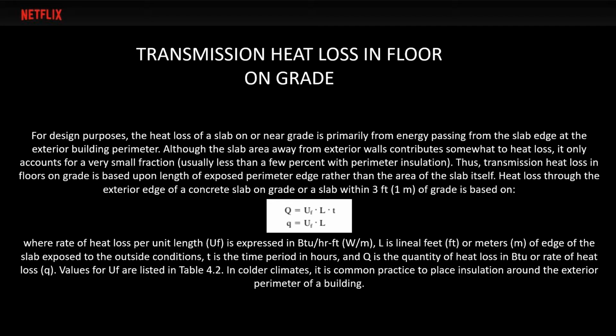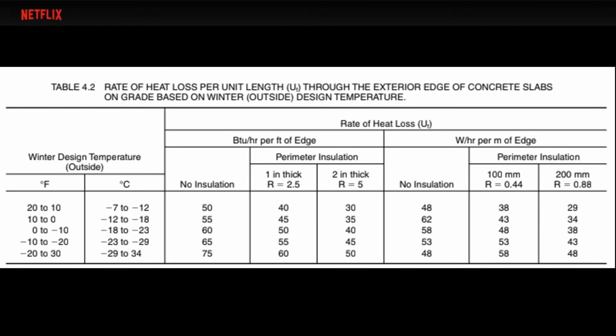So, here is the formula again, where the rate of heat loss per unit UF is expressed in BTU per hour per foot or W per meter. L is the lineal feet or meters of the edge of the slab exposed to the outside condition. T is the time period in hours, and Q is the quantity of heat loss in BTU or the rate of heat loss. Values of UF are listed in Table 4.2. In colder climates, it is common practice to place insulation around the exterior of the perimeter of the building. So, Table 4.2, rate of heat loss per unit length through the exterior edges of concrete slab on grade based on the winter outside design temperature. So, those are similar to the ones earlier.